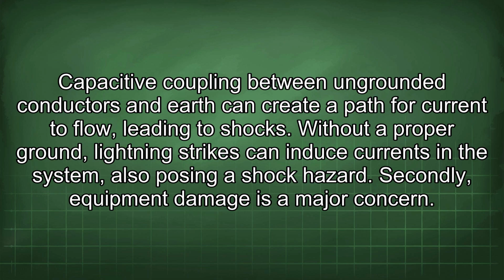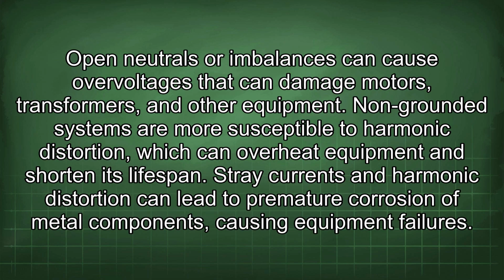Secondly, equipment damage is a major concern. Open neutrals or imbalances can cause overvoltages that can damage motors, transformers, and other equipment. Non-grounded systems are more susceptible to harmonic distortion, which can overheat equipment and shorten its lifespan. Stray currents and harmonic distortion can lead to premature corrosion of metal components, causing equipment failures.